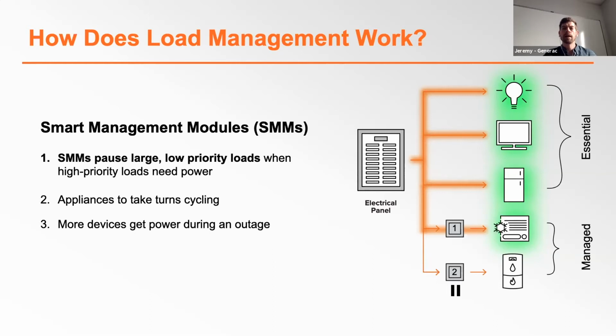But if your customer is unsatisfied with this, after a few outage experiences, they're missing the cycles in their hot water heater, it's pretty easy for you, the installer, to come back and reprioritize these, to assign the hot water heater as priority 1, AC unit as number 2. Lower priority circuits may have to wait for these higher priority circuits to turn off before power is available. In this case, what tripped this up was probably just the high startup draw from the AC unit. And I bet that after that was over, both could probably run simultaneously.